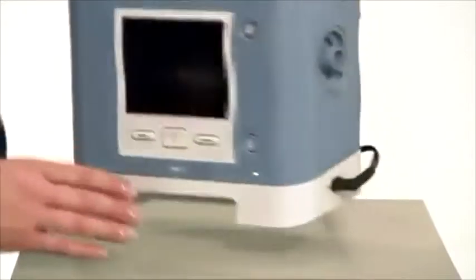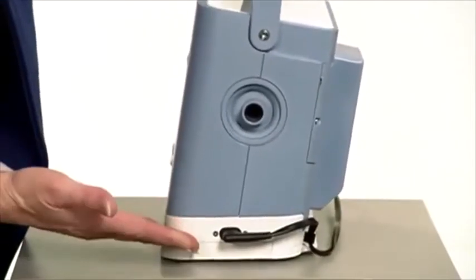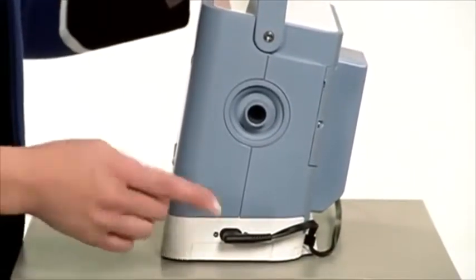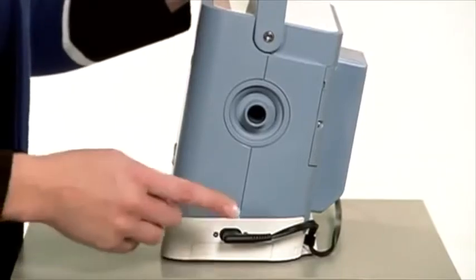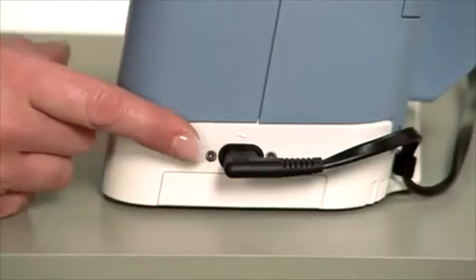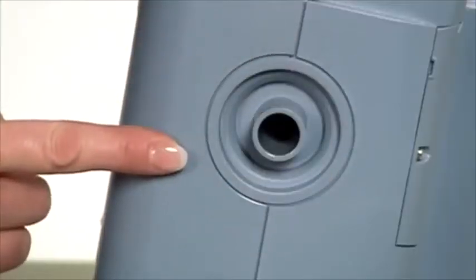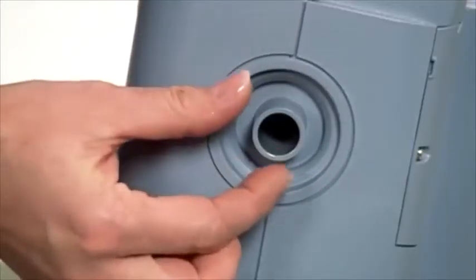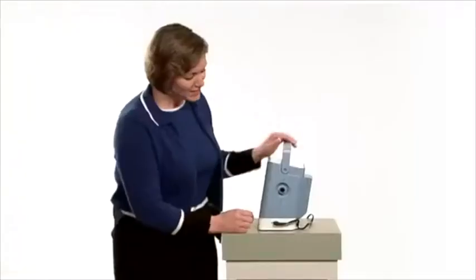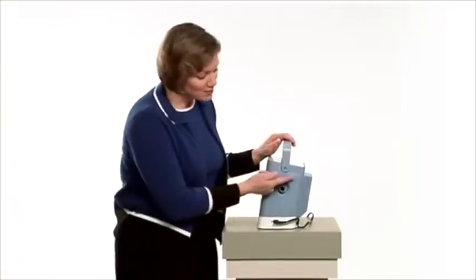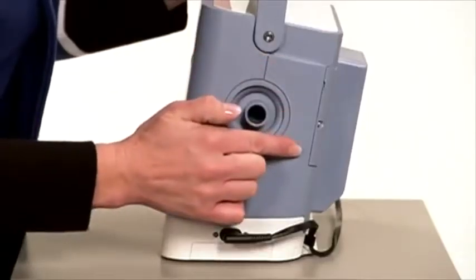On the right side of the unit, you can see the AC power inlet. When you plug the ventilator in, the socket end of the cord connects here. The round opening above it is the breathing circuit connection. The tubing fits snugly onto the ventilator here. The device we're looking at now is fitted with a passive exhalation porting block, which is this piece in the back. Let's look at the other side of Trilogy.